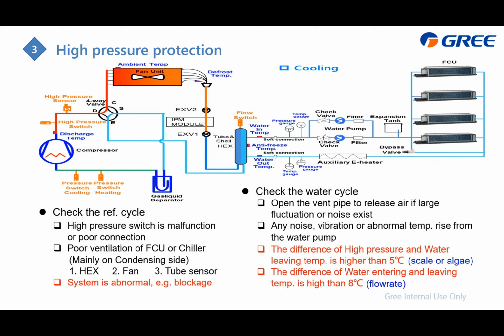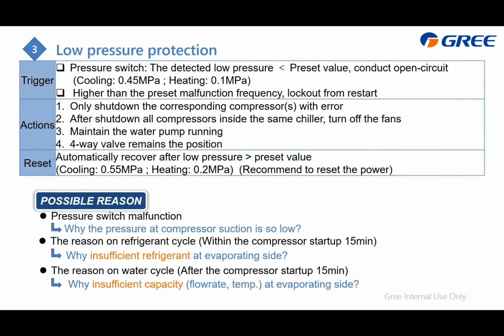And this is the summary of the high pressure protection. And the next is the low pressure protection, which is also only triggered by the pressure switch, which means the detected low pressure is less than our preset value, so the pressure switch goes to open circuit. In cooling mode, it is about 0.45 megapascal. Heating mode is about 0.1 megapascal. And these are the actions the system will take when it receives this open circuit. And it will be automatically recovered if the detected value is higher than this.